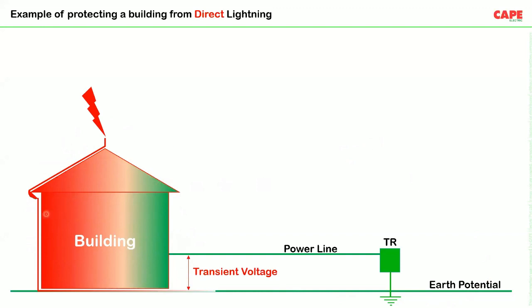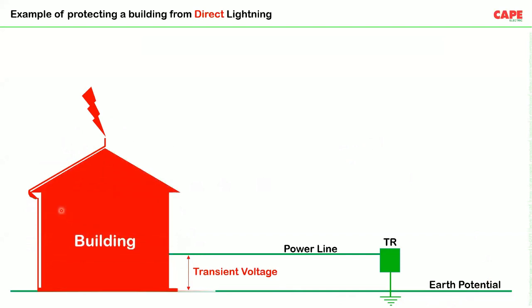So within the building, there is a potential difference created, and what you should do is to create an equipotential bonding in your building. If you create an equipotential bonding in your building, there is no potential difference between different metallic parts of the building. As a result, the building is safe. But look at the power line, which is coming from the transformer. The power line is carrying 230 volt. Maybe due to lightning, the potential of your building is, let's say, 50 kV. It can be even higher. So the potential of every metallic object in your building is 50 kV, and the line is only 230 volt. So there is a transient overvoltage between the earth and the connected line.